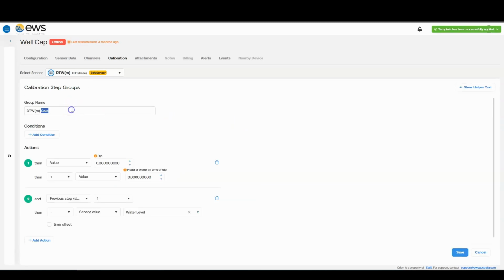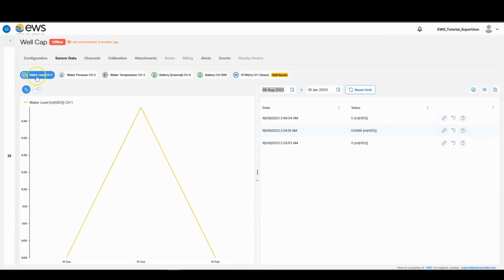We can then change the name of the calibration to the date of the calibration, insert the depth to water or dip measurement, and our first true sensor or meters head reading. Then click Save. We can then check the sensor data page to ensure that our calibrations have taken effect.